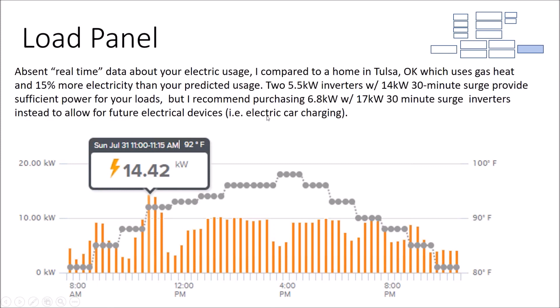So when we evaluated inverter selection, the main deciding factor was which battery inverter was set up for 600 volts. Most solar inverters are set up for 600 volts, but when I started evaluating the battery inverter market, I was shocked because most of these battery inverters' charge controllers - the voltage regulator between the array and the battery inverter - only went up to about 150 volts.